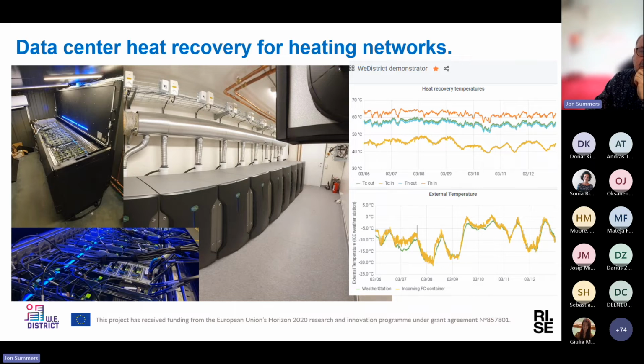The servers were running on a DC bus in the tank, so we only had to provide power to 2 power shelves. The power shelves were 3-phase, and what we did is we connected the 9 solid oxide fuel cells, because they were single-phase solid oxide fuel cells, in sets of 3 onto each of the 3 phases.